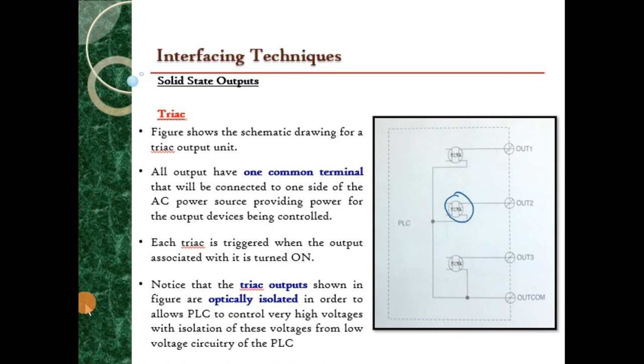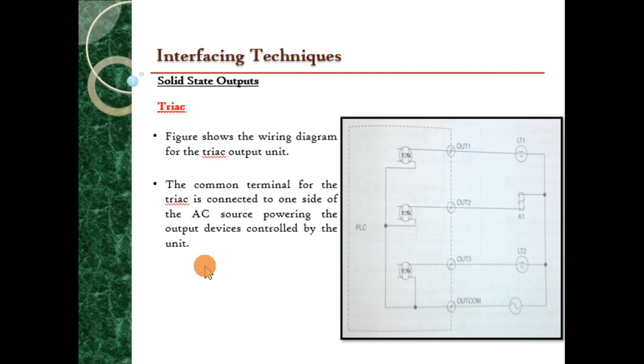So please notice that the triac outputs in this figure are optically isolated. It is optically isolated here in order to allow the PLC to control very high voltage with isolation of this voltage from low voltage circuitry of the PLC, because the PLC is a low voltage circuitry, but maybe the output is a high voltage circuitry. That's why I use the isolation type of circuit here. This is an example of a wiring diagram for the triac output unit. The common terminal for the triac is connected to one side of the AC source, powering the output devices controlled by the unit. It is connected to one common power source here to control the output devices.